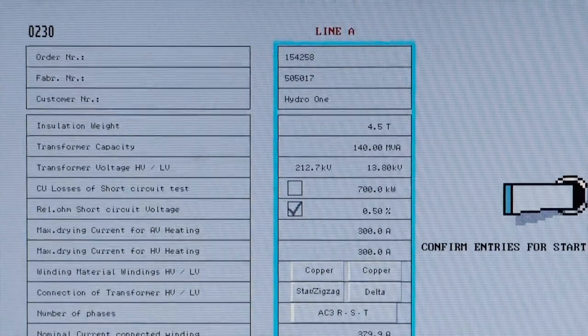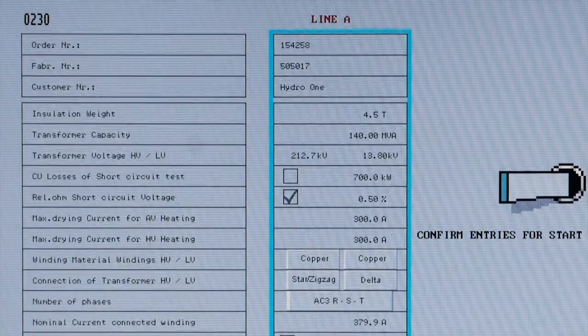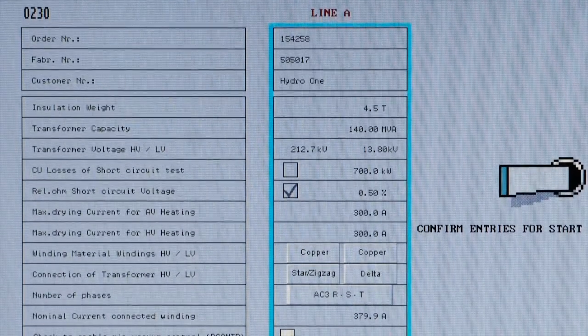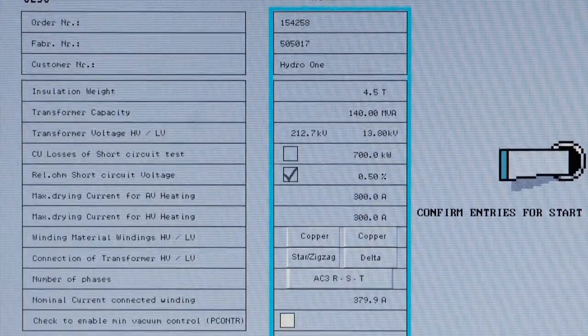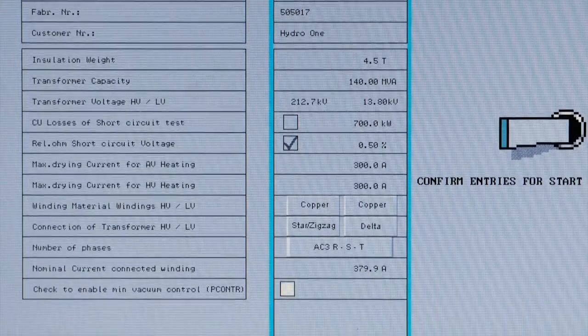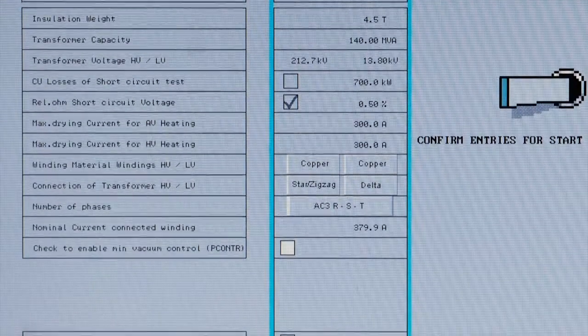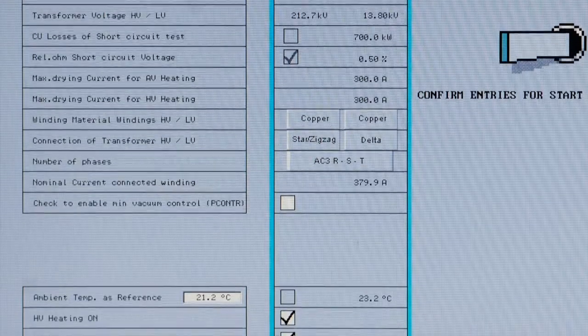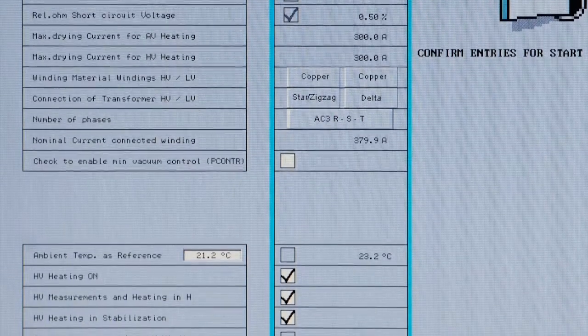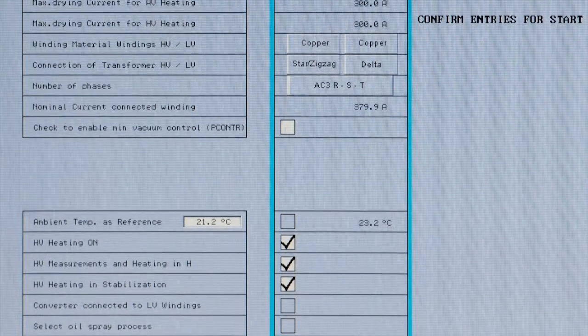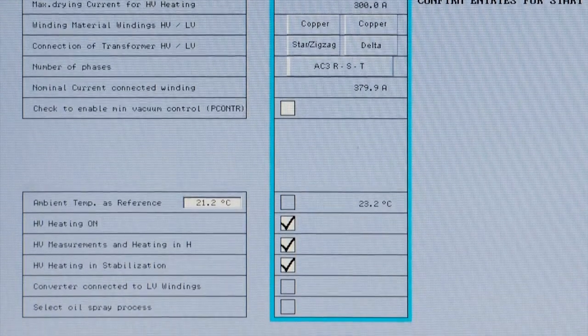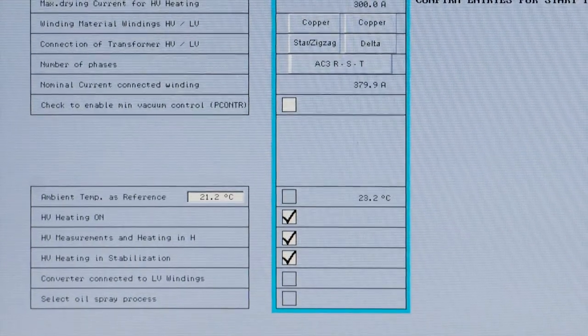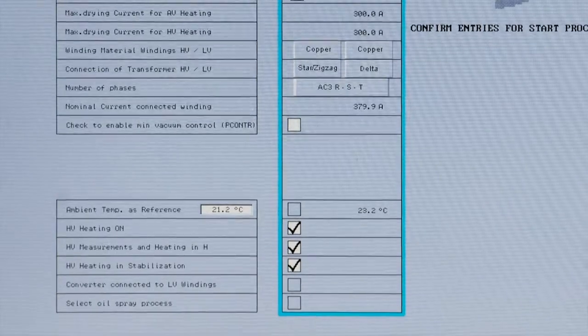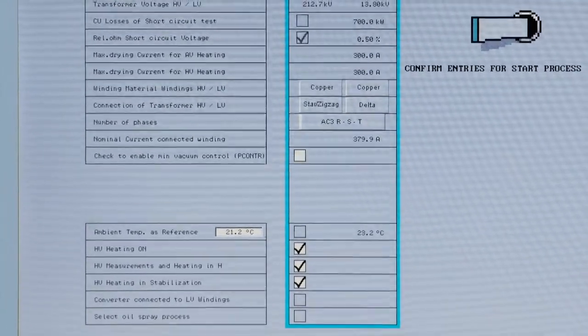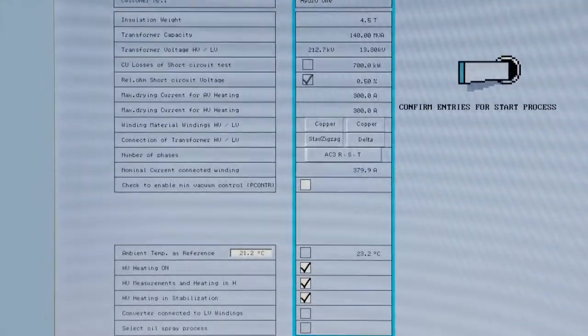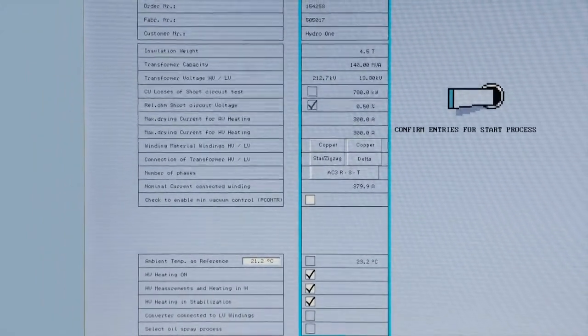technical data sheet. These data consist of the following: customer reference information, which contains the identifier for the transformer; insulation weight, as accurately as possible as it is used by the VZ406 to calculate the final water extraction rate; transformer capacity value in MVA that is used to calculate the nominal current of the transformer; transformer voltages for the high voltage and low voltage values in kilovolts, which are also used to calculate the nominal current; copper losses of short circuit test. The load losses, if they are known, should be entered as kilowatts.